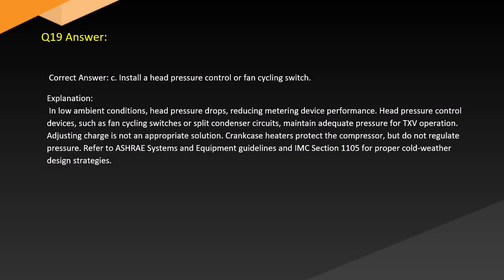Answer. Correct answer: C. Install a head pressure control or fan cycling switch. Explanation. In low ambient conditions, head pressure drops, reducing metering device performance. Head pressure control devices, such as fan cycling switches or split condenser circuits, maintain adequate pressure for TXV operation. Adjusting charge is not an appropriate solution. Crankcase heaters protect the compressor but do not regulate pressure. Refer to ASHRAE Systems Equipment Guidelines and IMC Section 1105 for proper cold weather design strategies.